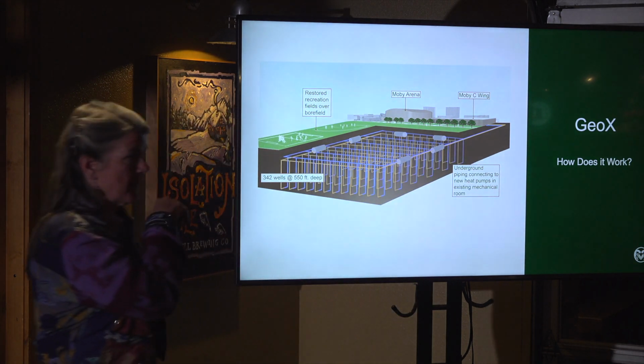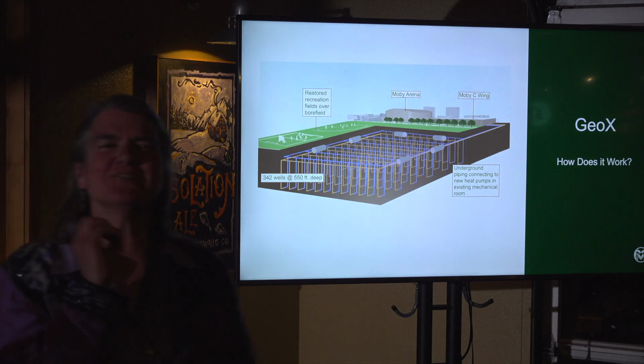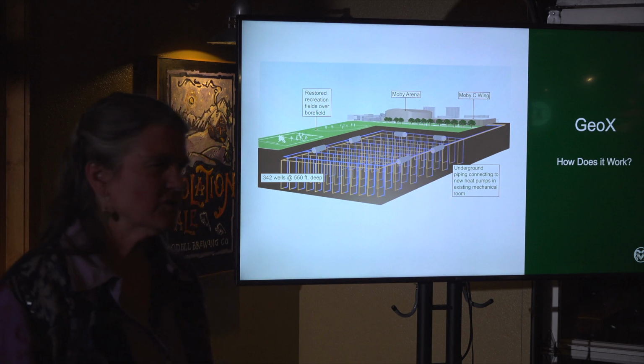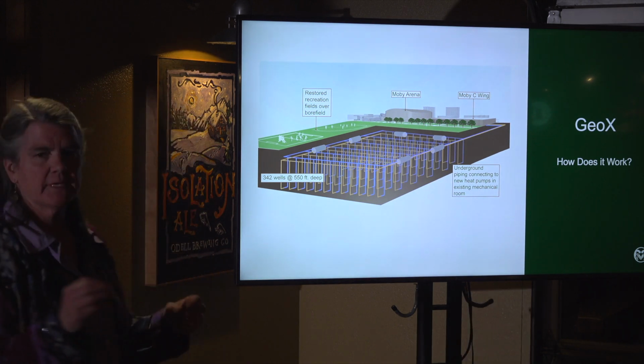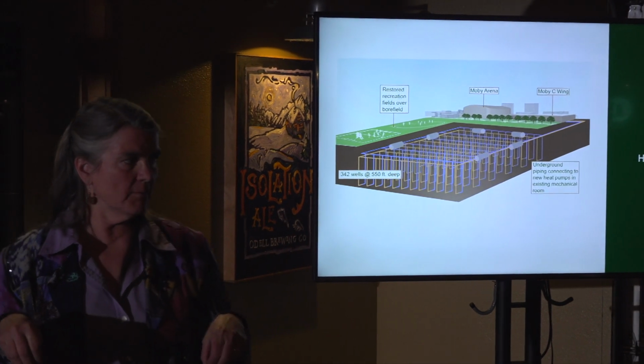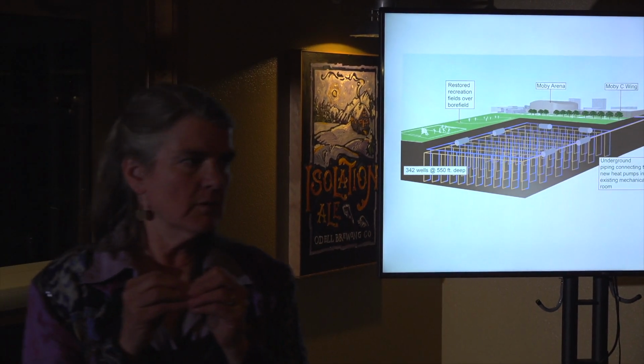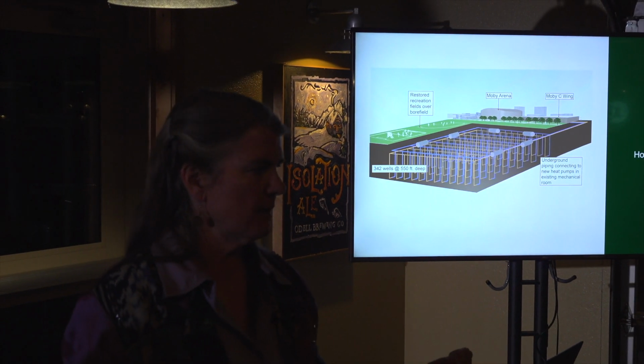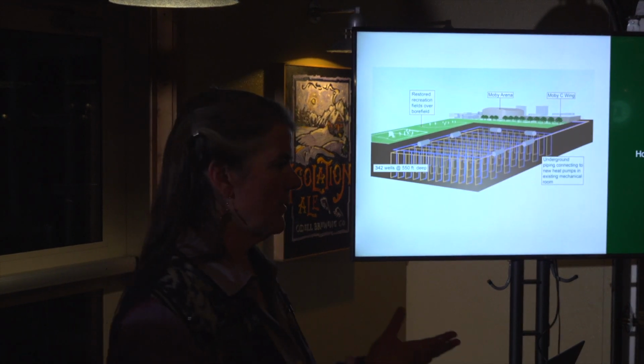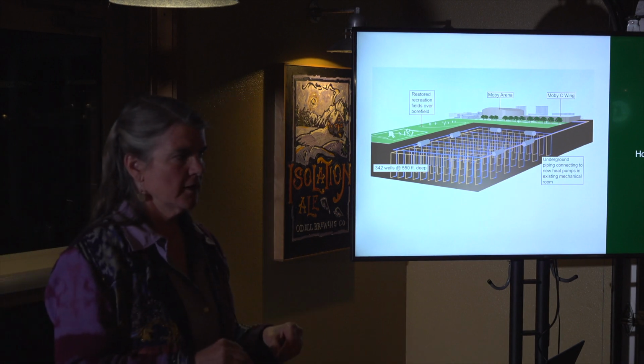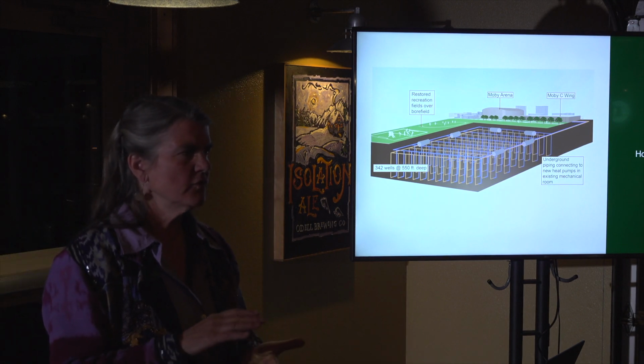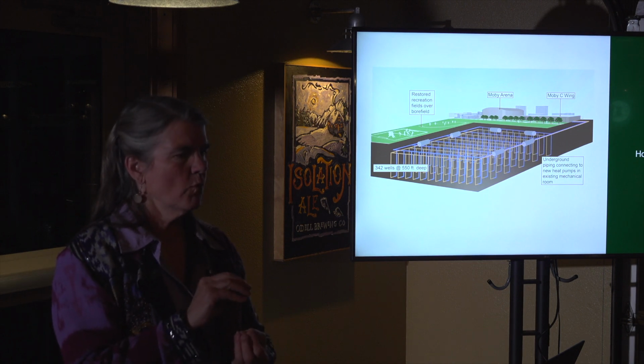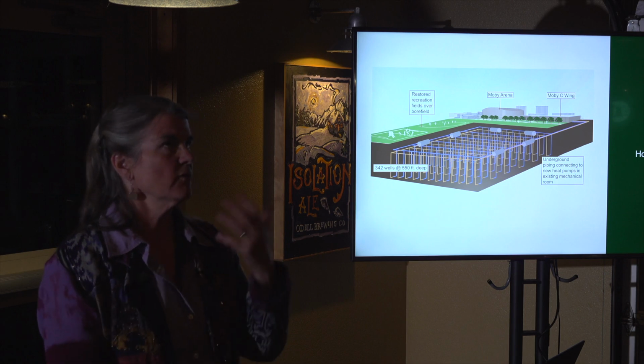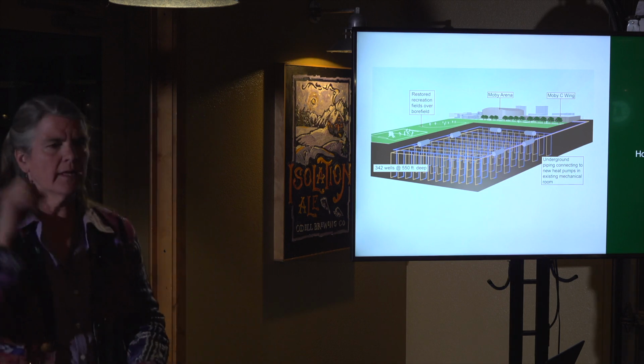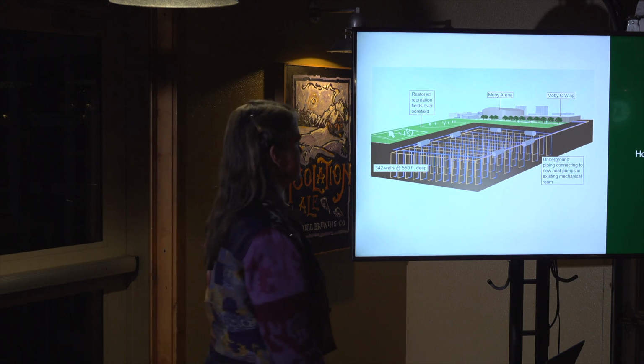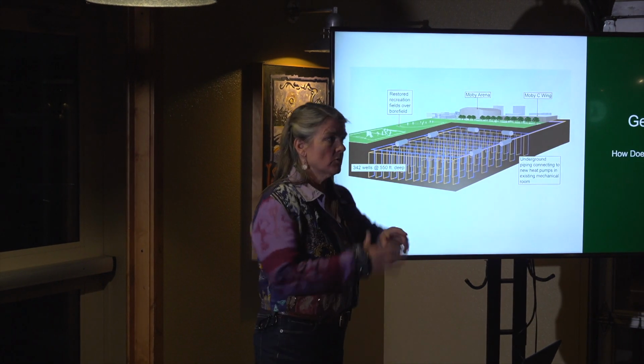Someone asked about the spacing between boreholes—I knew that question would come up. I think it's 20 feet, maybe 25. Spacing matters a lot because thermally the boreholes can start to interfere with each other: in summer you're dumping heat into the ground, so it gradually warms up. Folks at Poudre School District monitored their well field and said it rises a few degrees, but by the time it starts getting warm, it's fall and they want to pull heat back out of the ground, so it reverses. That's part of why we went deeper, to keep the boreholes far enough apart.